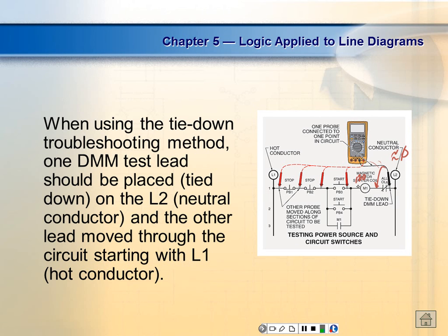You need to check on this side, you need to check here and you need to check there, because what you're trying to do is eliminate. Not only are you trying to eliminate the devices, you're trying to eliminate the wire. And there's a lot of times wires go bad. Just a bad crimp, right? Just a bad termination. It works, and all of a sudden something.